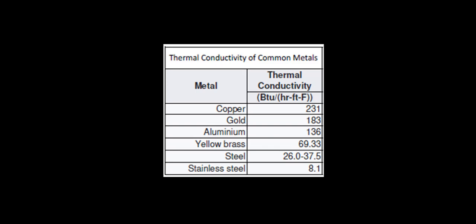Some cases may be the reduction of galvanic corrosion between dissimilar metals, or possibly used in coastal resilience in marine locations. However, the majority of the coils seen in HVAC equipment are built with copper tubes and aluminum fins. The combination has the most effective heat transfer as well as the lower cost.